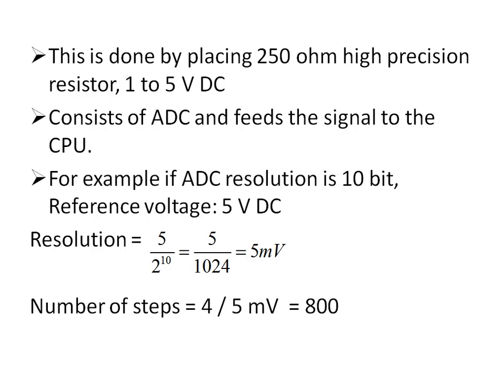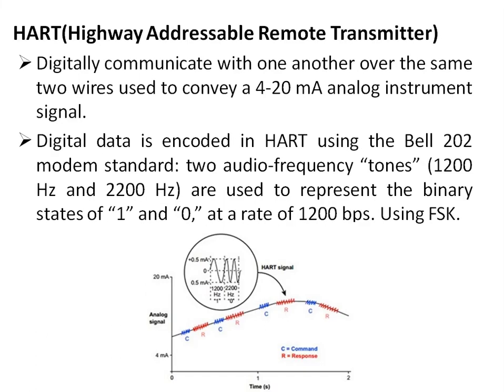For example, if the ADC resolution is 10-bit and the ADC reference voltage is 5 volts, then the resolution of that ADC is 5 millivolts. In the 1 to 5 volts DC range, corresponding to 4 to 20 milliampere, this gives 800 steps.